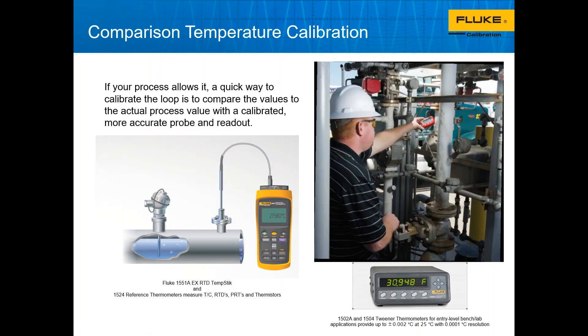Another popular method is comparison calibrations — you leave the probe in the process and take the signal off of it, comparing it to a more accurate handheld reference device. This example uses a 1524 reference thermometer. You connect to a nearby port, make a temperature reference measurement, compare what the process is telling you versus what this device reads, and make an adjustment to the transmitter. This lets you make a very accurate comparison while allowing your process fluid to be the temperature source.